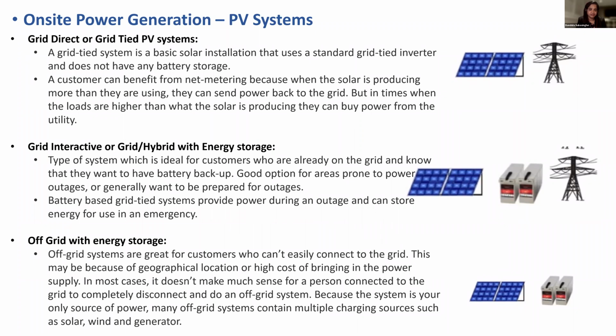Grid tied systems connect to the grid through an import-export meter, so if you're not using power, it exports to the grid. If there's a mains power shutdown, you can't use the PV system anymore, because there's an automatic shutdown system that shuts down the inverters - you don't want power feeding into the grid if someone is working on it to fix a power failure. We don't want power in those networks for safety reasons, so one drawback is that it can't be used as emergency power.